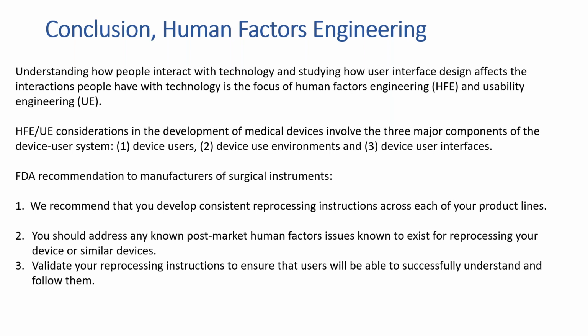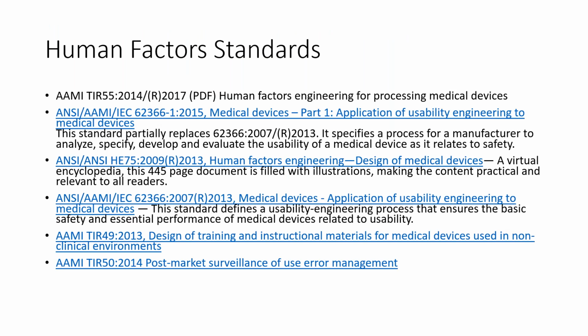And as we saw from the FDA recommendation for cleaning, it said that we recommend that you develop consistent reprocessing instructions across each of your product lines. You should address any known post-market human factor issues known to exist for reprocessing your devices or similar devices, and validate your reprocessing instructions to ensure that the user will be able to successfully understand and follow them. I think the important part, especially with item number 2, is that post-market surveillance is really something that the user needs to feed back to the FDA, and that requires collaboration between the device manufacturer, the hospital users, and going back to the FDA so that we all could resolve some of the issues.